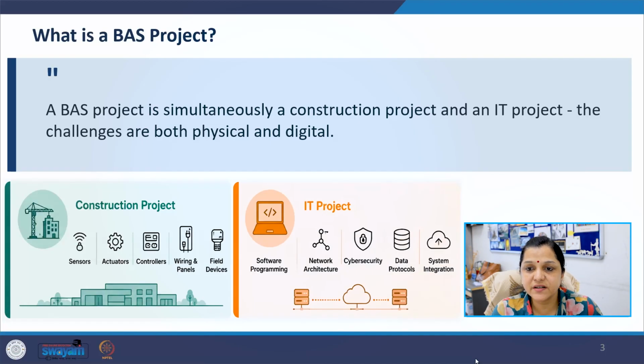From the construction perspective, we have physical elements such as sensors, actuators, controllers, cables, control panels, and field devices. These components must be installed correctly inside the building. At the same time, the BAS also depends heavily on software programming, network architecture, communication protocol, cyber security, and data integration. This dual nature creates challenges, as both have their different types of challenges.